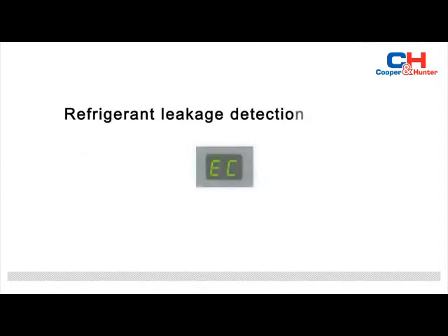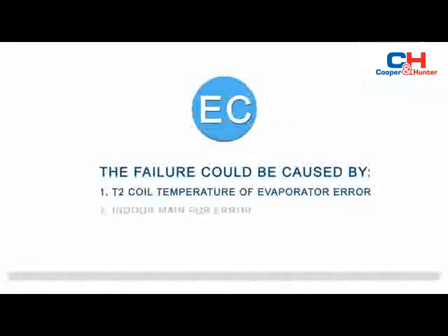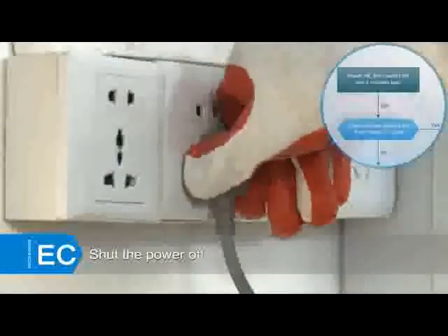When the indoor unit displays EC, that indicates a refrigerant leakage detection error. The failure could be caused by: 1) T2 coil temperature of evaporator error, 2) indoor main PCB error, or 3) refrigerant system error.